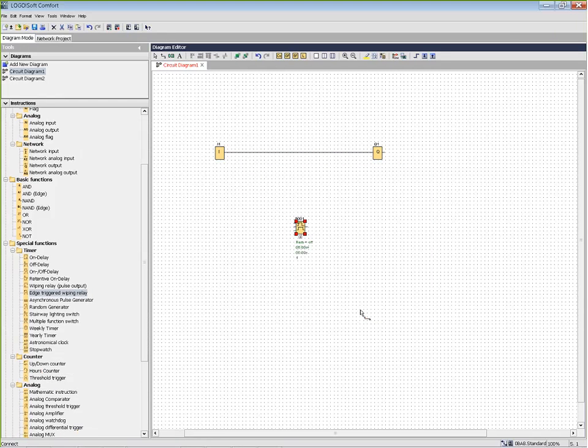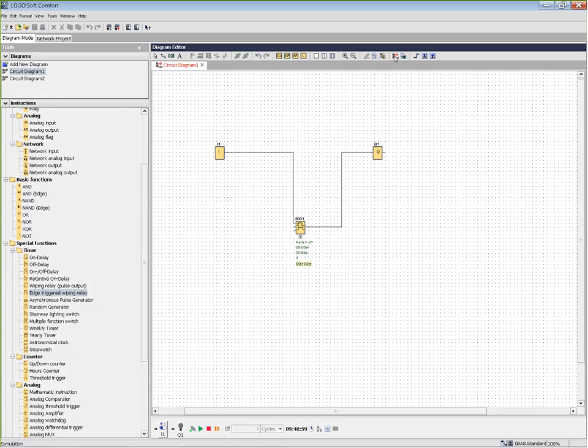To edit the program, all I need to do is click my arrow there and click what I want to edit. I'll take the wire that was connected to the output and run it through the timer first, connect the wire from the output of the timer to the output on the Logo, and simulate that. Now when I push the button, it turns on the fan, and it's running for 5 seconds, and then it stops. That's kind of neat. Essentially, the Logo Comfort software is like that, where we just drag things and connect them up together, and then away they go.